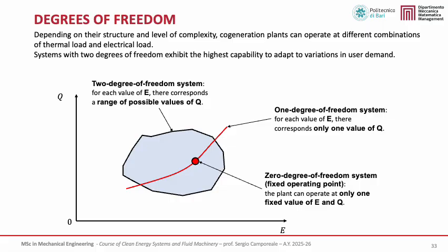Systems with 2 degrees of freedom exhibit the highest operational flexibility. For a given electrical output, a range of thermal outputs is possible, meaning the operating point can move within an area of the energy plane. This greater flexibility allows better adaptation to variations in user demand and facilitates both heat-led and power-led operation, which is particularly important for maximizing heat utilization and primary energy savings.